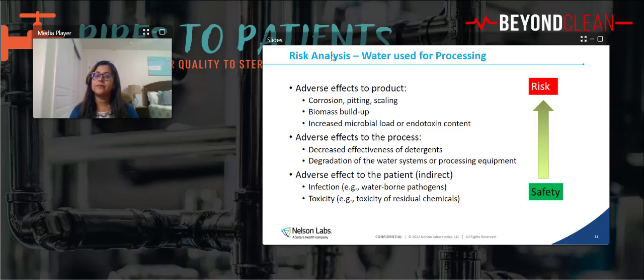Something to think about. Not when the expiration date is there, but when you start to see degradation. Something we are also talking to AER manufacturers about is that you have an expiration date, but depending on how it's used, where it's used, and what kind of water hardness is coming from the city through these filters, that's the degradation that's going to happen on the filter. And that needs to be communicated by the manufacturer to the healthcare facilities.